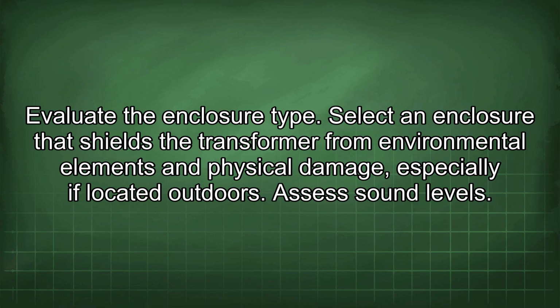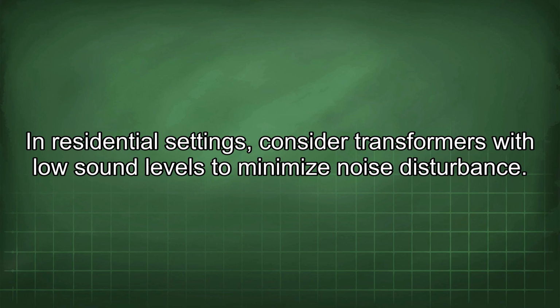Evaluate the enclosure type. Select an enclosure that shields the transformer from environmental elements and physical damage, especially if located outdoors. Assess sound levels. In residential settings, consider transformers with low sound levels to minimize noise disturbance.